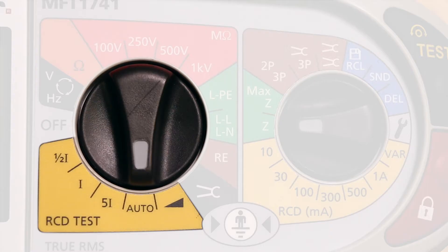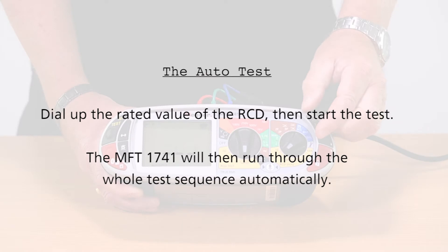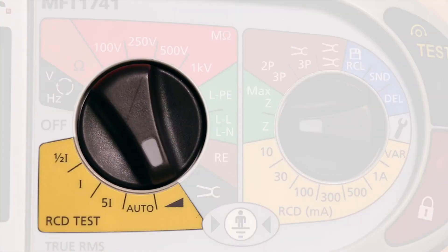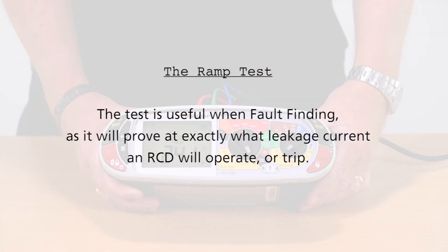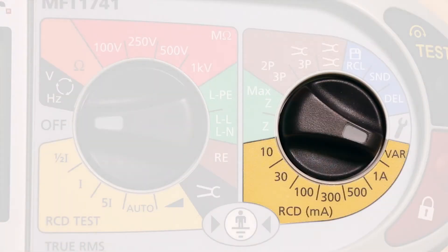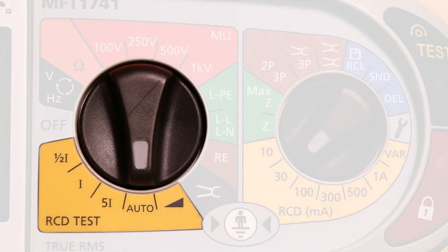We also have the auto test facility, where you can dial up the rated value of the RCD, start the auto test, and the unit will run through the whole sequence. Then we have the ramp test, which is particularly useful when fault finding because it will prove at exactly what leakage current an RCD will operate or trip. There is also a variable RCD test which we will look at later.